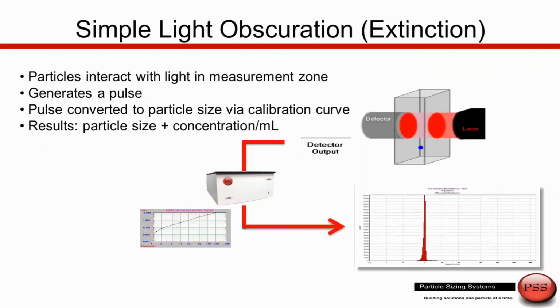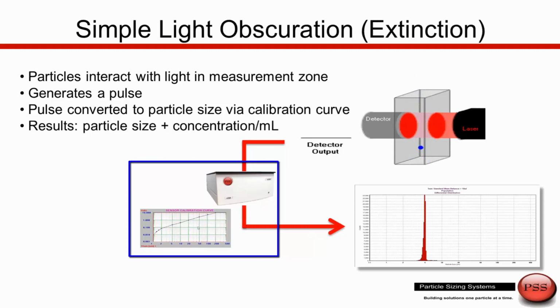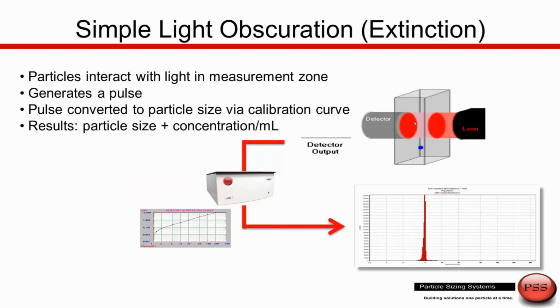The instruments used are liquid particle counters. And the instrument specified in these ISO standards is a light obscuration or light extinction particle counter. With basic light extinction, the particles pass through a light source. This generates pulse heights, and a pulse height analyzer, through the use of a calibration curve, then transforms these pulse heights into a particle size. So we flow the liquid through the sensor, the particles generate pulses, and we convert that to particle size, and one at a time, we count and size these particles. This is a sensor based only on obscuration or extinction, where we're essentially looking at the shadow cast as the particle passes through the sensor.